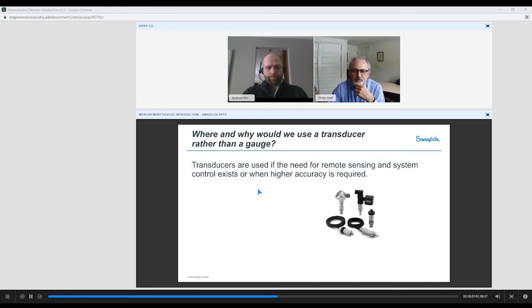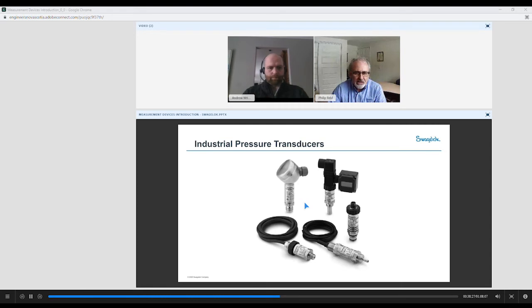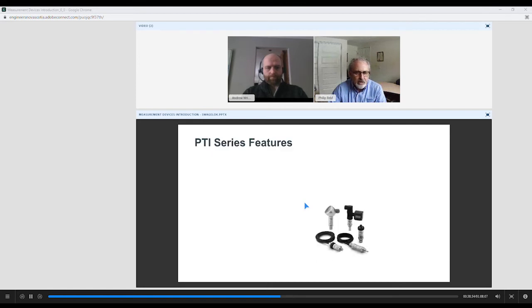And so the big thing about it is that a transducer can be used where you need remote sensing in a system, you need a higher level of accuracy that we'll talk about, or it may be in an area that is hazardous and you're not going to be able to get in there to read a pressure gauge and you want to have these readings sent back to a control panel or back to a control room. So again, many different applications, explosion proof, etc., intrinsically safe.